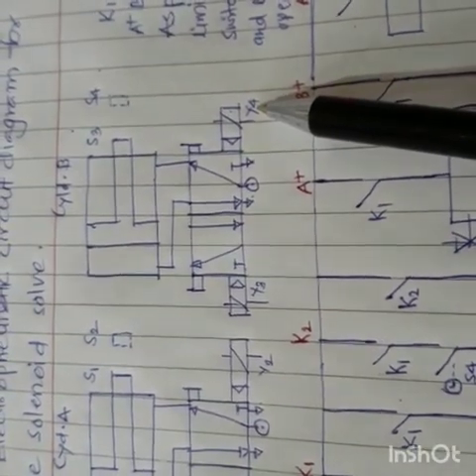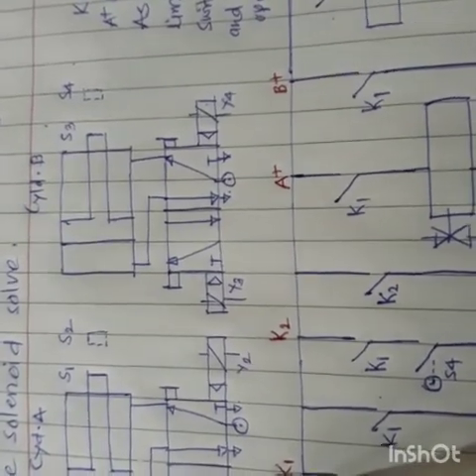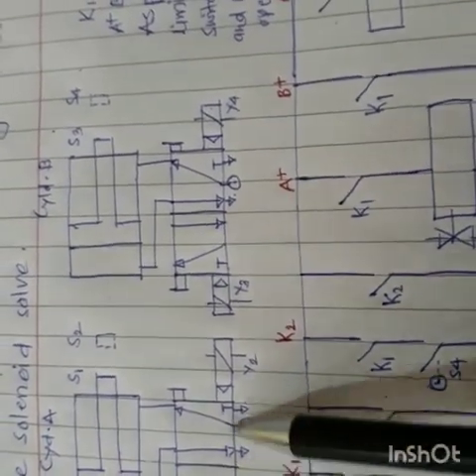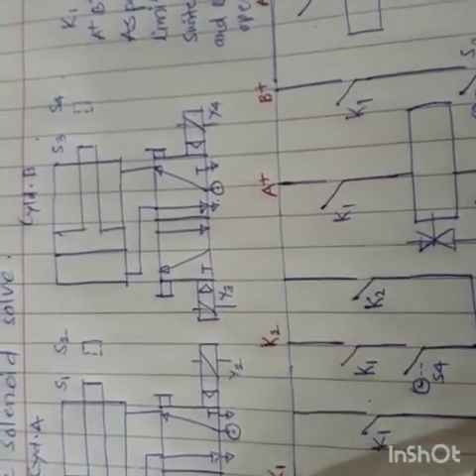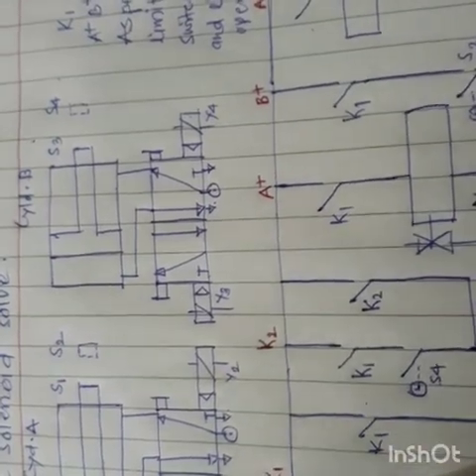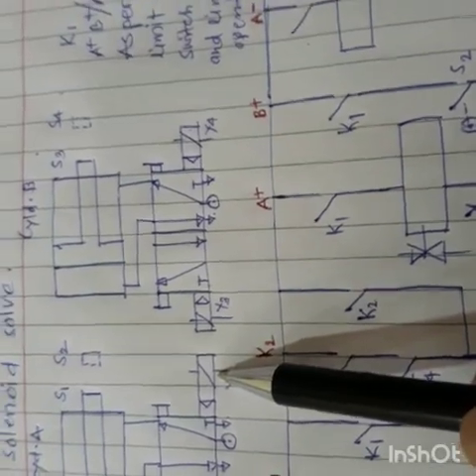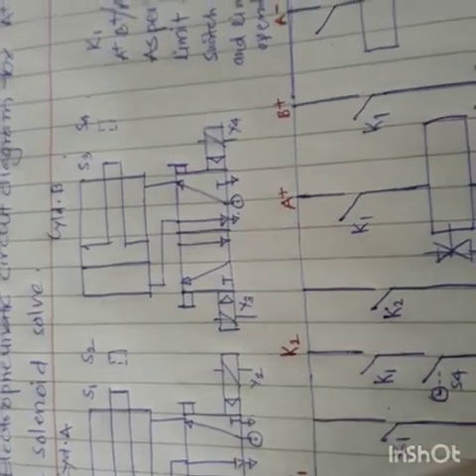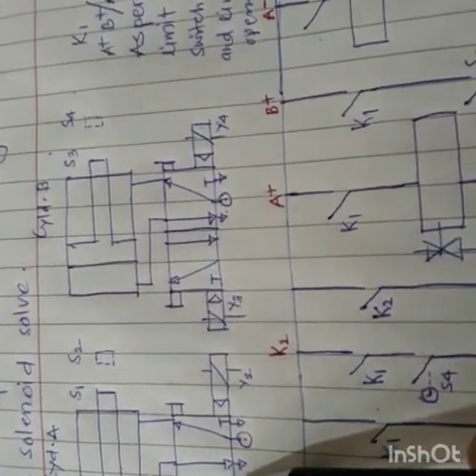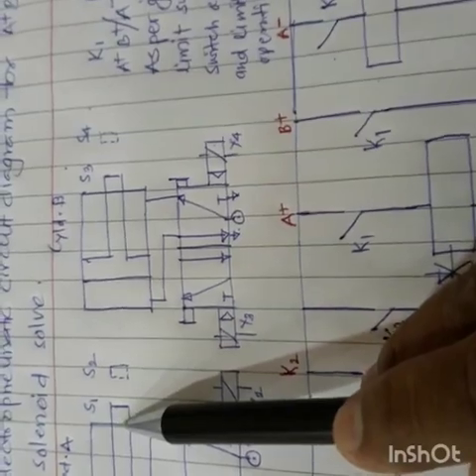We have to take care that when you actuate solenoid Y1, Y2 must be de-energized. So at a time these two solenoids cannot both be energized. When A plus is completed, that is Y1 is energized, the piston will move from the left hand side to the right hand side and touches S2.